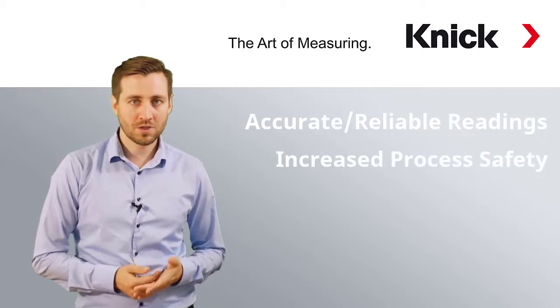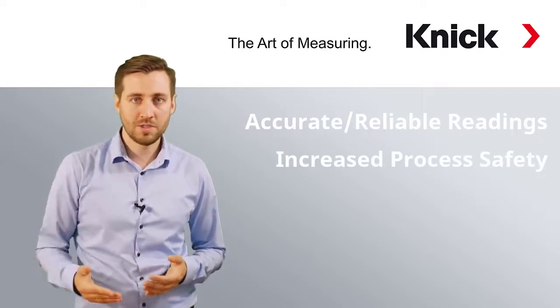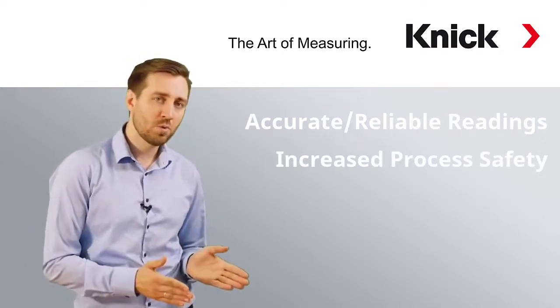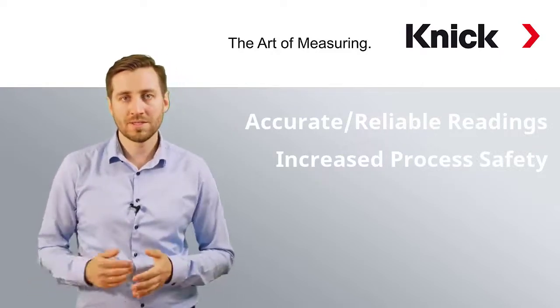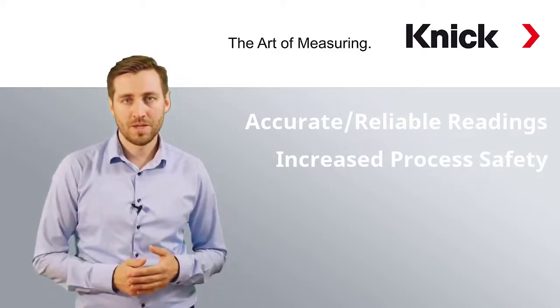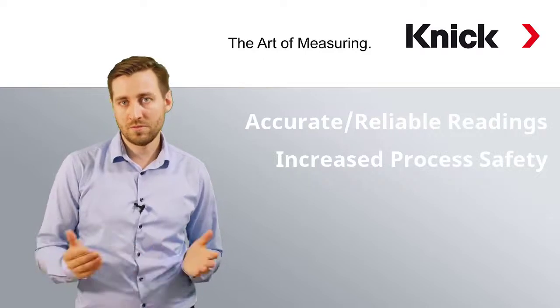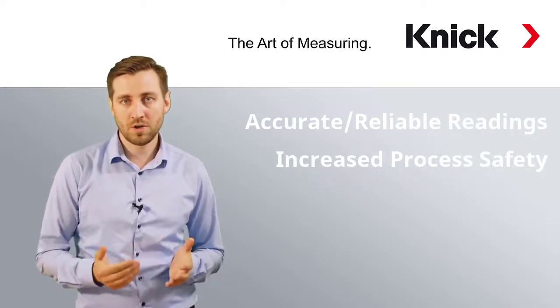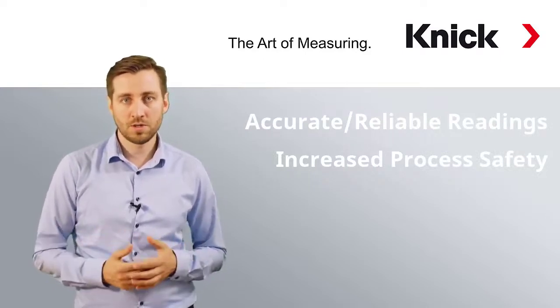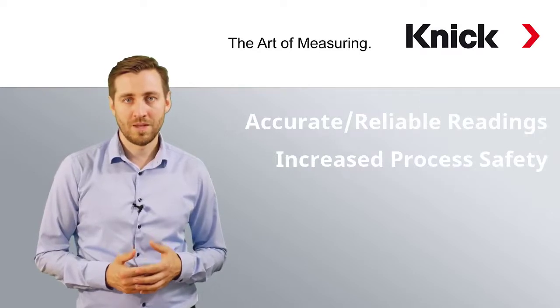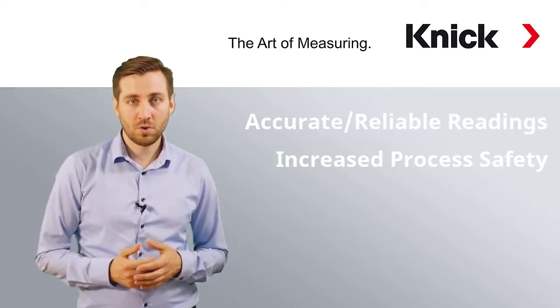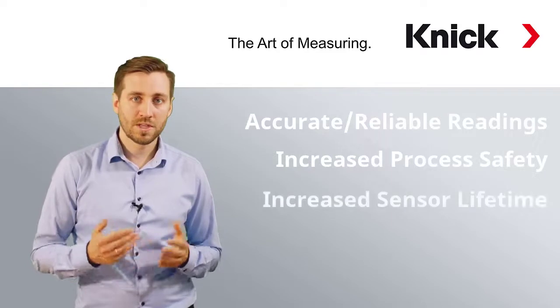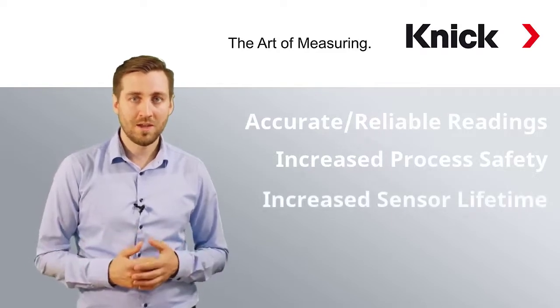The automated calibrations will result in more process safety because you have less manual work, more automated and standardized procedures. This will reduce the risk that you have to destroy or discharge a product because you're not meeting the quality requirements. In addition, you can even save costs further because the sensor lifetime will be increased and the maintenance is reduced.